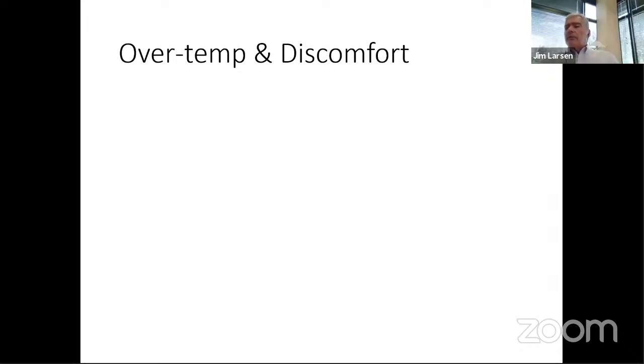It's been my experience that when the room gets up to temperature, when there's enough solar gain into the space that it shuts off the thermostat, in essence shuts off the heating plant, then you're riding along free. But it doesn't know if you're 2 degrees above the thermostat or 10 degrees above. It's not making an analysis on that, and that's something you've got to be cognizant of, as a question of how much window area you've got and all those details.